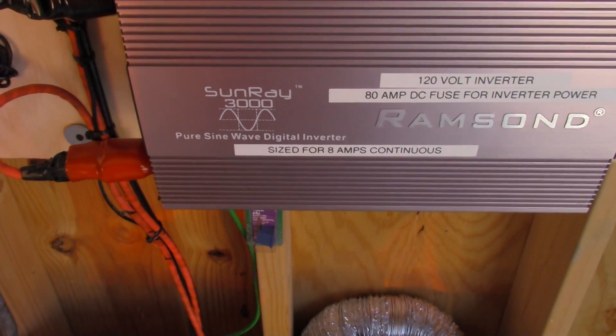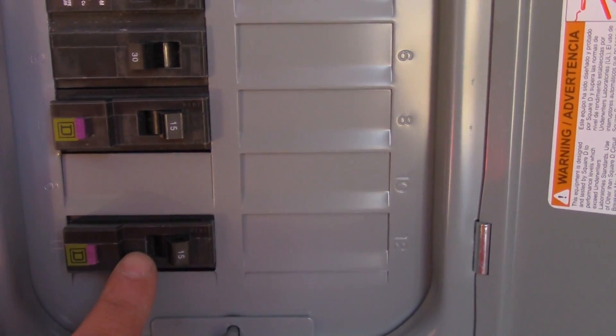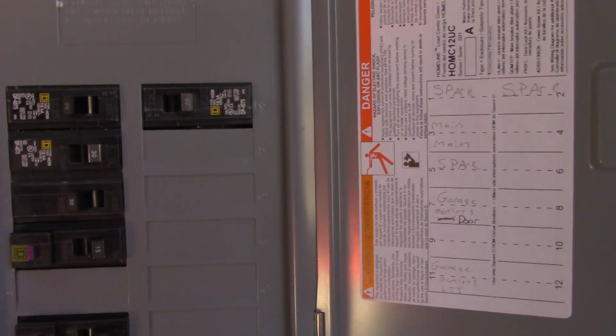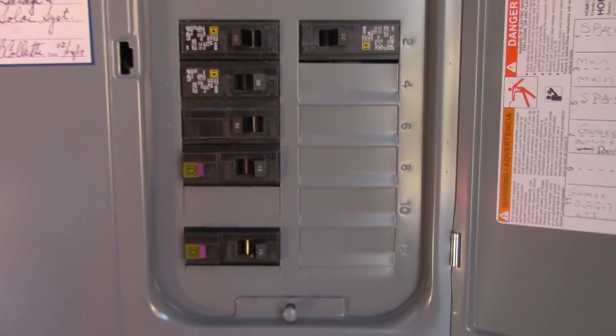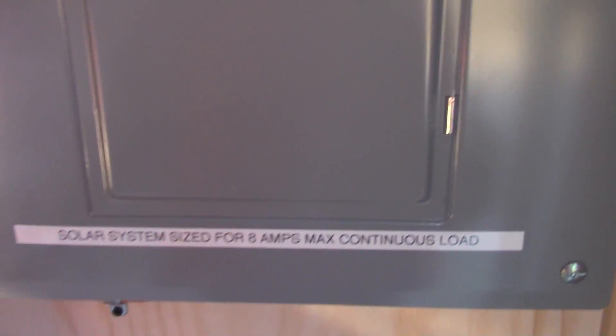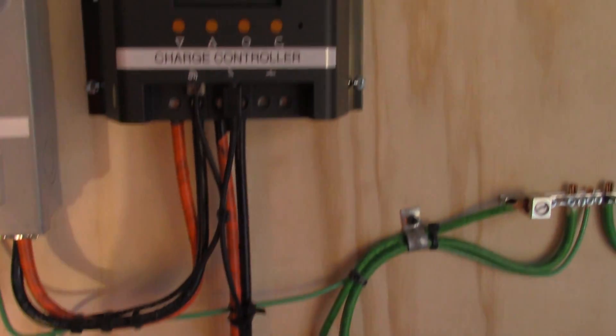Then we have another fuse here, so this will only allow 80 amps to go through that wire. And here are our circuits for the garage — we installed these combo GFCI and arc fault circuit breakers. These are just filling the space — they're spare circuits. This is our main, feeding the panel. And these are branch circuits powering the garage. This here gets connected to a load from the charge controller.